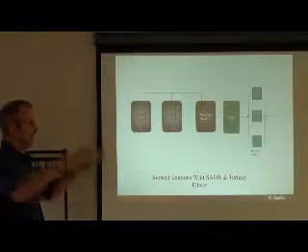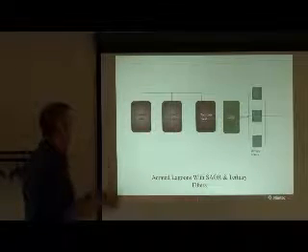So our next option was using an aerated lagoon. We're adding air into those existing lagoons through an aeration system, just floating aerators in the lagoons. We're adding oxygen in there to promote biological activity. Then we have what we call a polishing pond, which is really just a big settling pond. So you mix everything up, aerate it, and then you let it settle out. And then we go into what we call the SAGR, which is a submerged attached growth reactor. All that does is ammonia treatment.